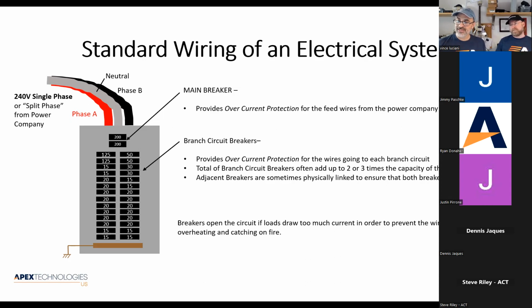One thing that is really interesting is if you total up the breaker values of these individual breakers, they often exceed the main breaker by quite a bit, 2 or 3 times higher. And you say, well, how can that be? It's like I have the possibility of pulling 400 or 600 amps, yet my service is only 200 amps. Well, the reason is that we know you're not going to have everything on all the time in the house. There's going to be some things on.